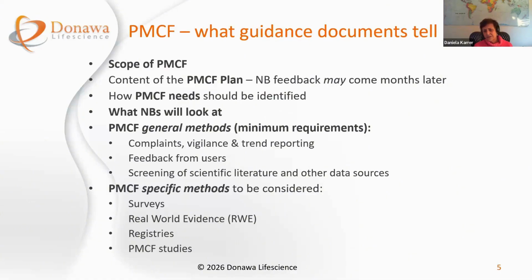The PMCF plan should be submitted at the time of the CE marking, but it's quite likely, at least this is our recent experience, that you won't receive feedback from notified bodies, and sometimes it's going to take months, even if it's negative and the data and the plan is considered insufficient. This tells us that you should do everything you can to do it right from the beginning. So this exercise should be done quite right from the start. Otherwise, you'll be waiting for feedback that may come who knows when.